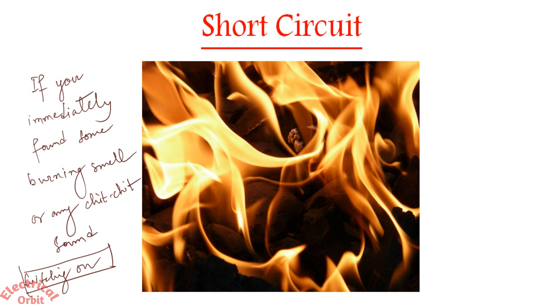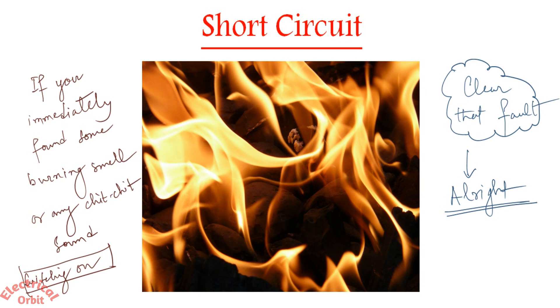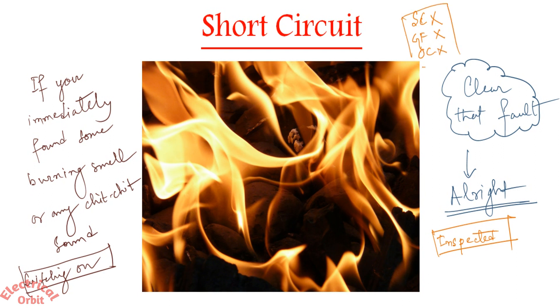If you have inspected all these things and found that everything is okay — no short circuit, no ground fault, no overload current — and your MCB is still tripping, then you may conclude that there is some spring problem or a problem with the tripping mechanism of the MCB. The solution is to replace the MCB.